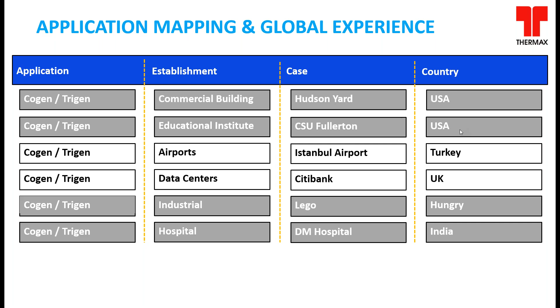Deenanath Mangeshkar Hospital is a hospital in Pune. It is an 800 bed hospital with 3 absorption chillers of 350 tons of refrigeration each, driven by exhaust gas and hot water from engines. There are 3 engines, 2 working and 1 standby, catering to the total power requirement of the hospital complex, while the chillers handle its cooling needs. This installation has been operating for the last 6 years, saving a lot in electricity cost and drastically reducing their CO2 footprint.